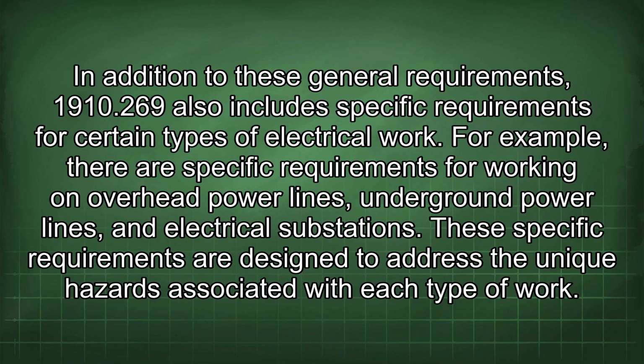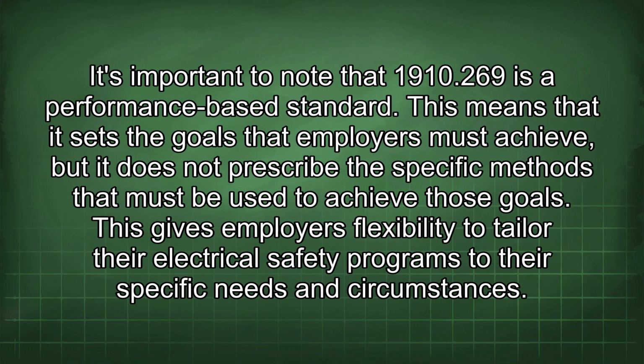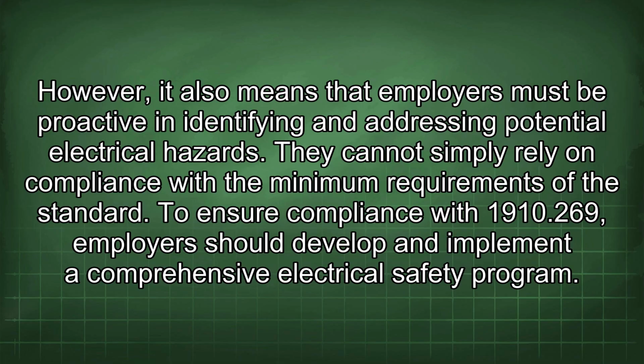In addition to these general requirements, 1910.269 also includes specific requirements for certain types of electrical work. For example, there are specific requirements for working on overhead power lines, underground power lines, and electrical substations. These specific requirements are designed to address the unique hazards associated with each type of work. It's important to note that 1910.269 is a performance-based standard. This means that it sets the goals that employers must achieve, but it does not prescribe the specific methods that must be used to achieve those goals. This gives employers flexibility to tailor their electrical safety programs to their specific needs and circumstances. However, it also means that employers must be proactive in identifying and addressing potential electrical hazards. They cannot simply rely on compliance with the minimum requirements of the standard.